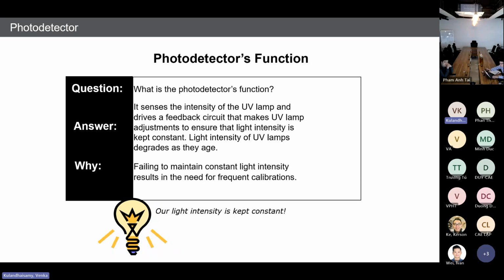So I hope you guys know what a photodetector is. This slide explains the photodetector function. It senses the intensity of the UV lamp and drives the feedback circuit that makes UV lamp adjustments to ensure that light intensity is kept constant. Light intensity of UV lamps degrades as they age. Failing to maintain constant light intensity results in the need for frequent calibrations. That means drifting.